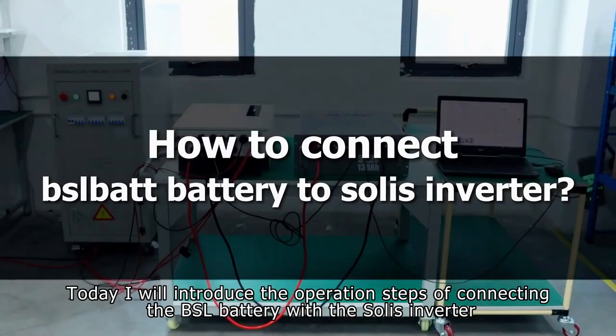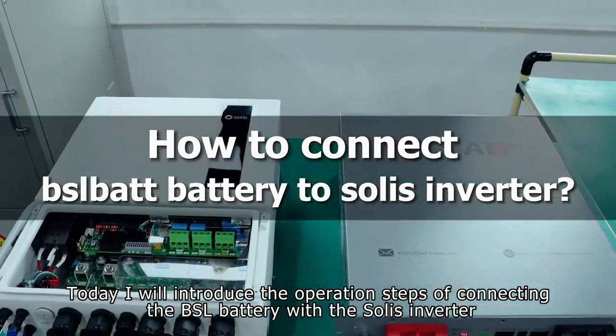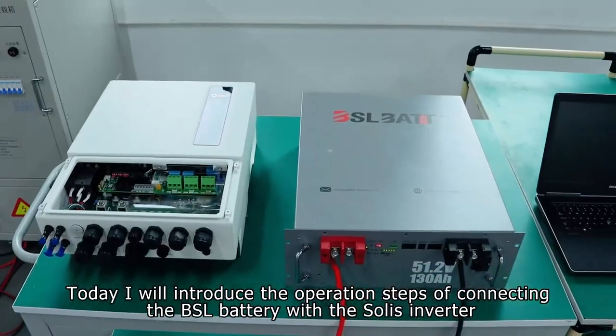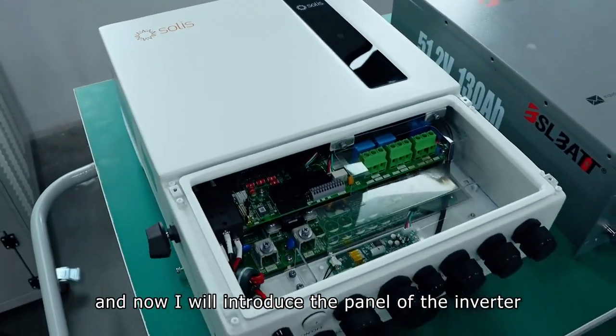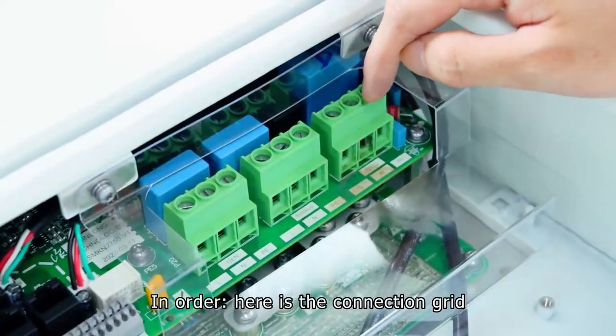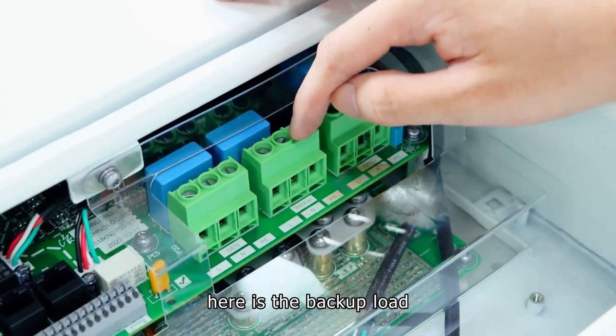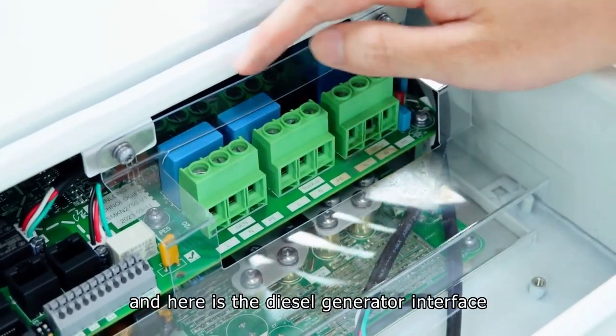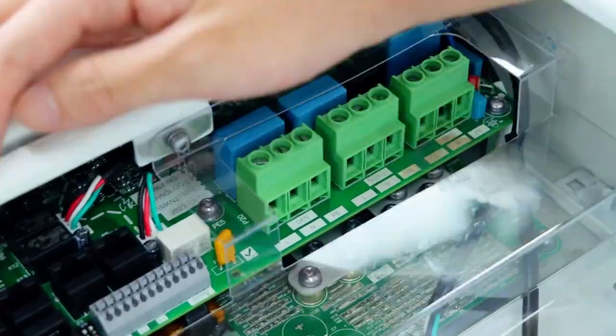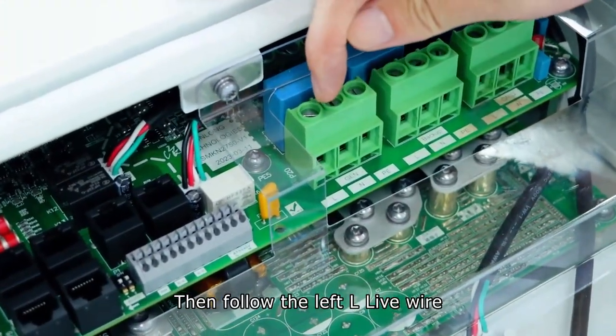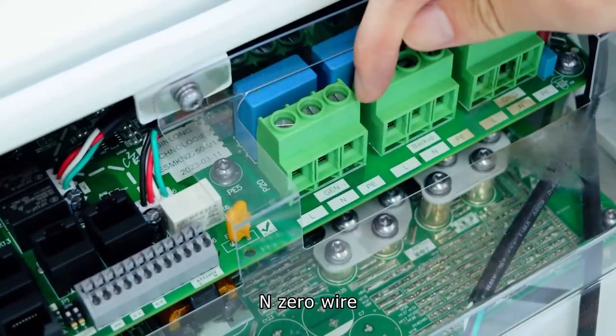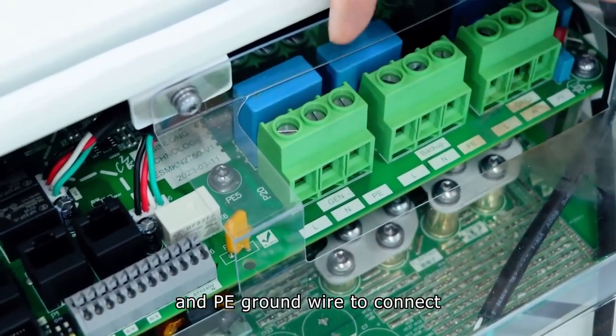Today I will introduce the operation steps of connecting the BSL battery with the Solis inverter, and now I will introduce the panel of the inverter. In order, here is the connection grid, here is the backup load, and here is the diesel generator interface. Then follow the left L live wire, N wire, and PE ground wire to connect.